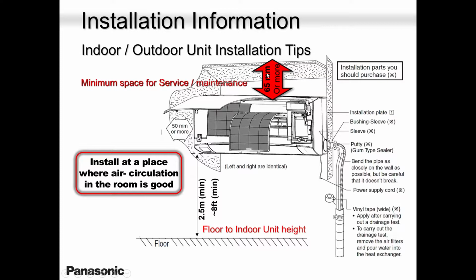So what happens when you don't have space here? When you squeeze this indoor unit so high that there is air getting trapped here, it's going to put the outdoor unit into sleep mode, into standby, because all the time heat is trapped here. And now what? The sensor is saying, I'm happy. I'm more than happy. Go to sleep. Meanwhile, the guy downstairs here in this area is freezing.